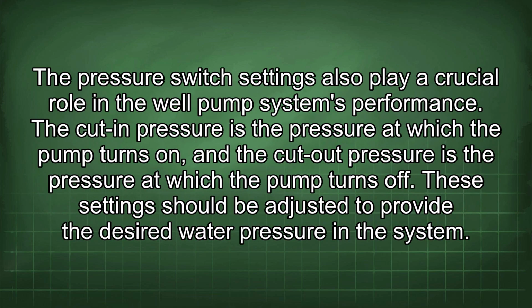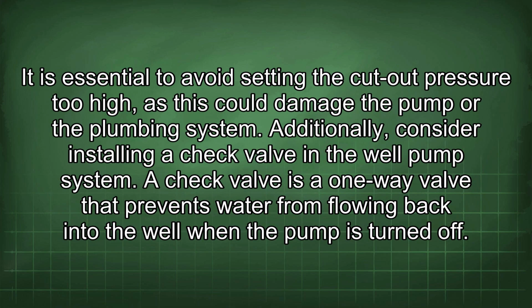The pressure switch settings also play a crucial role in the well pump system's performance. The cut-in pressure is the pressure at which the pump turns on, and the cut-out pressure is the pressure at which the pump turns off. These settings should be adjusted to provide the desired water pressure in the system. It is essential to avoid setting the cut-out pressure too high, as this could damage the pump or the plumbing system.